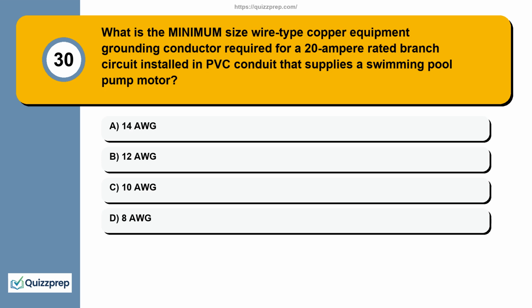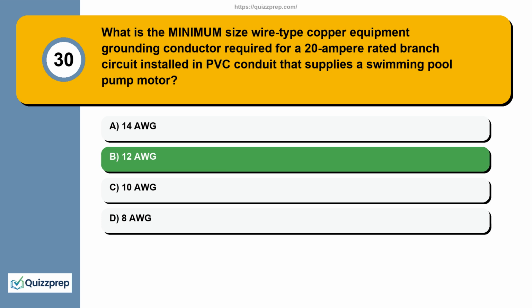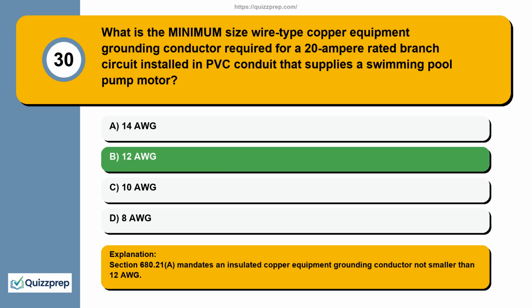Question 30. What is the minimum size wire-type copper equipment grounding conductor required for a 20 ampere rated branch circuit installed in PVC conduit that supplies a swimming pool pump motor? 14 AWG, 12 AWG, 10 AWG, 8 AWG. Section 680.21(A) mandates an insulated copper equipment grounding conductor not smaller than 12 AWG.